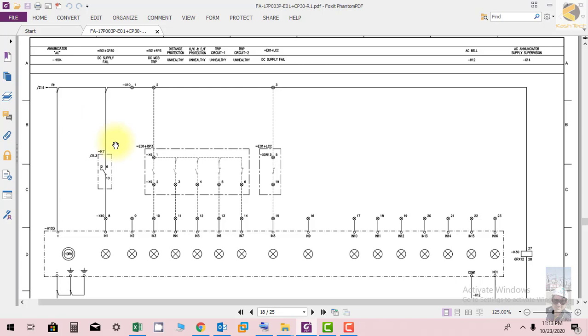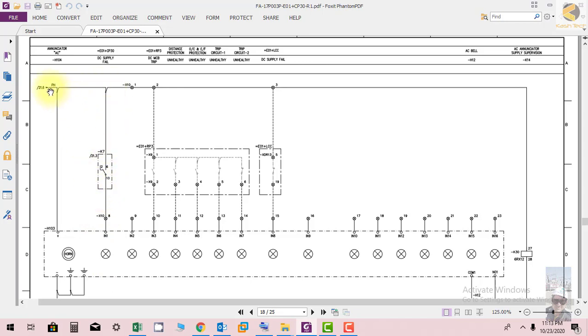If DC supply fails, K7 is picked up and it will give alarm. DC supply fail is shown on the AC annunciator, which is fed from AC phase and neutral. In the same way, if any protection fails because the supply fails or there is an internal hardware failure, the indication is provided by AC supply.